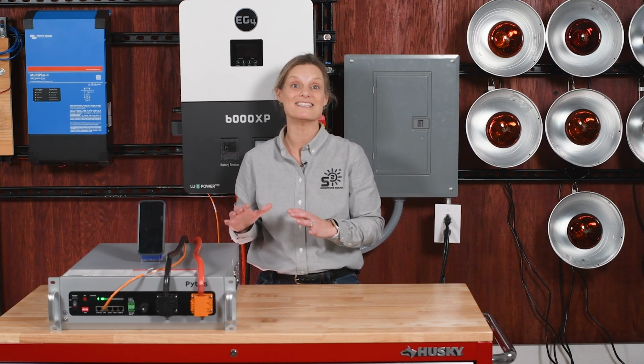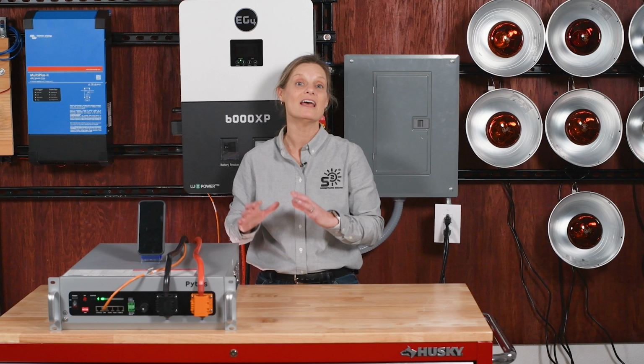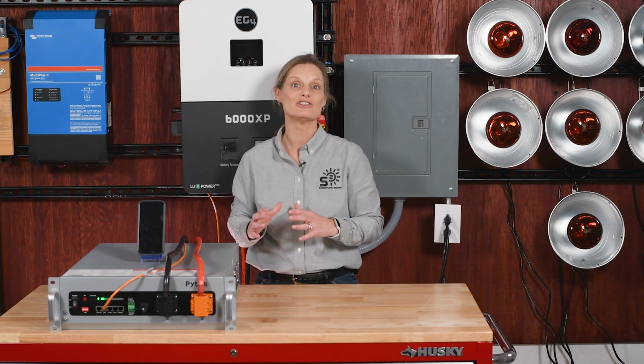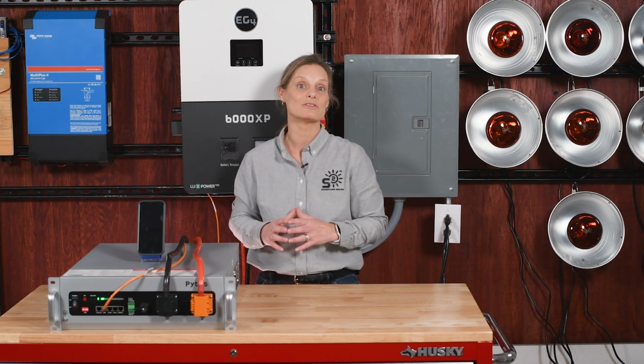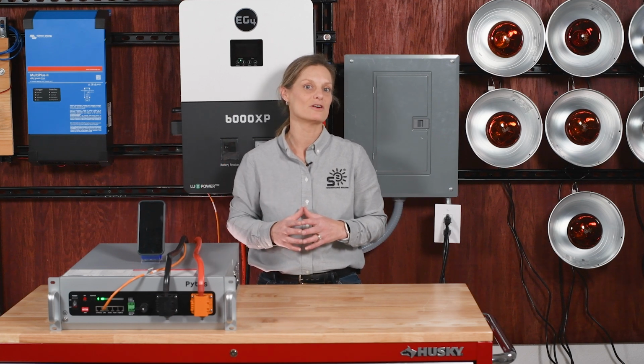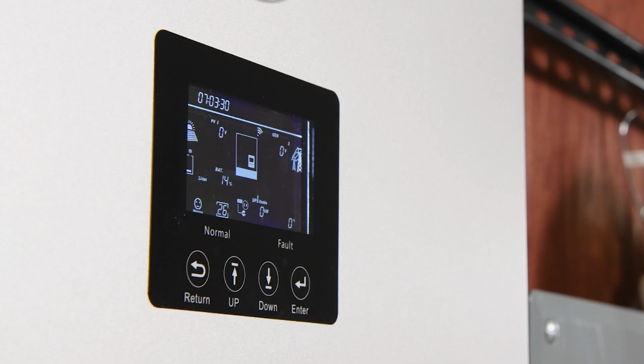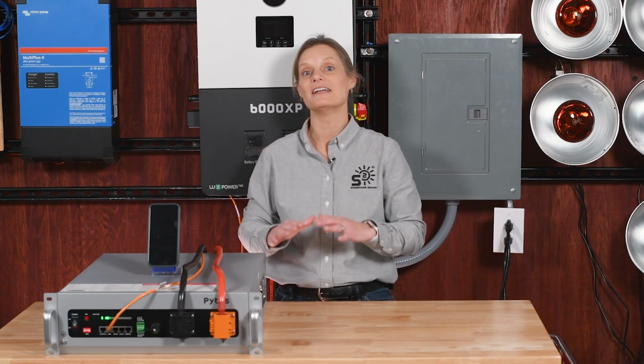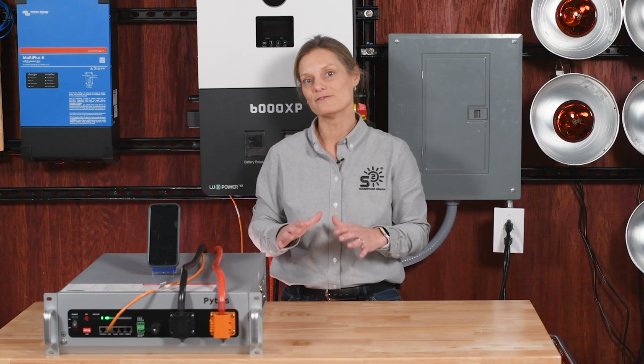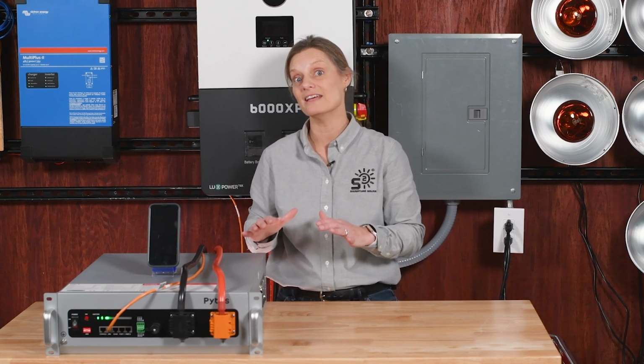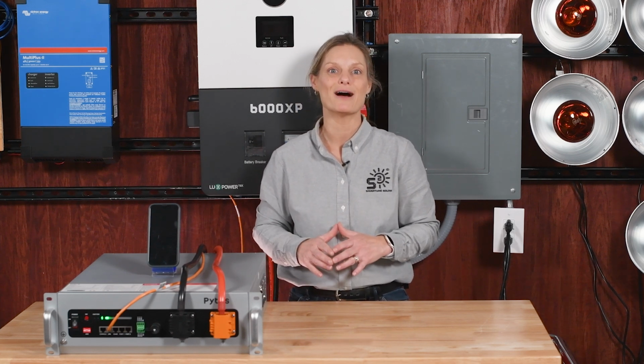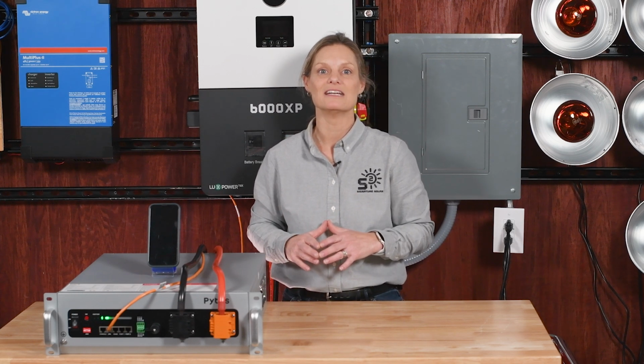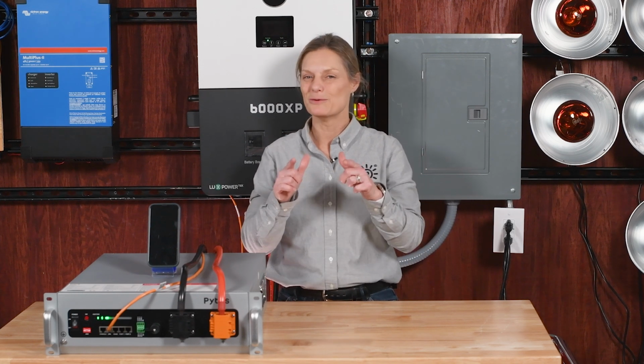The Pytes BMS is designed to automatically stop discharging at 10% state of charge, ensuring a safe depth of discharge at 90% unless overridden by the inverter. As we observed, the inverter display verified that the battery's BMS shut down at 14% state of charge, a little earlier than expected. However, this still ensures that it adheres to the safety threshold, confirming that the BMS is functioning within the safety parameters established by Pytes to maintain a 90% depth of discharge, providing you with added peace of mind.